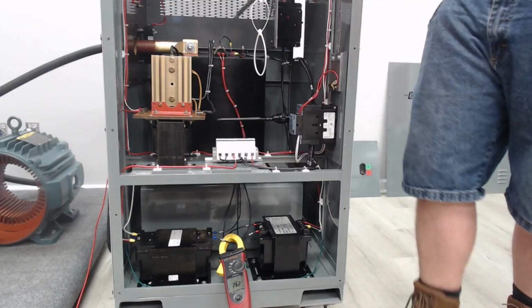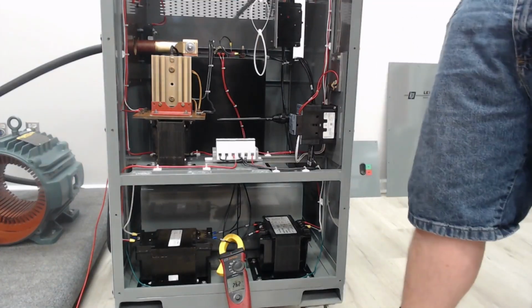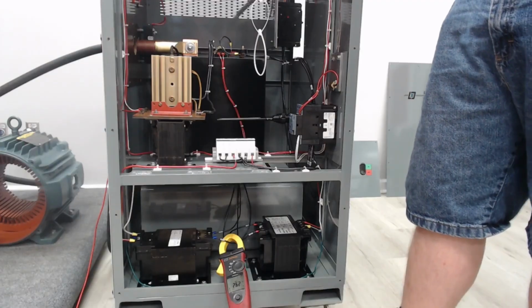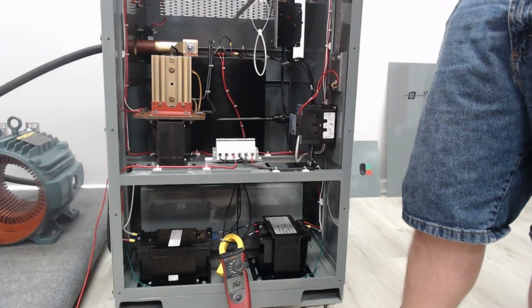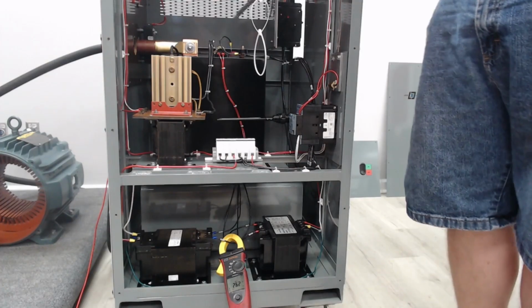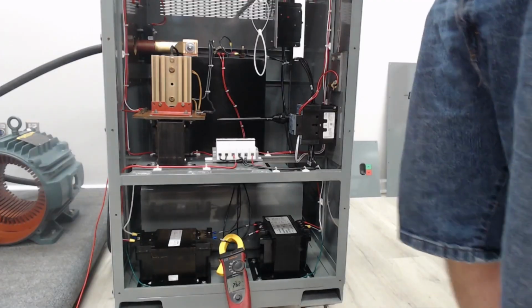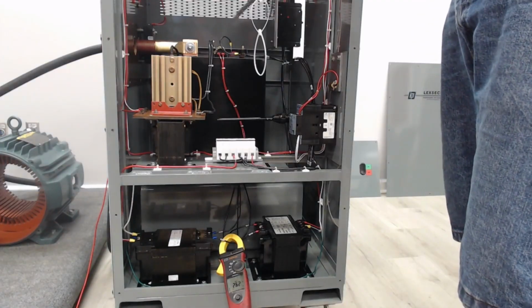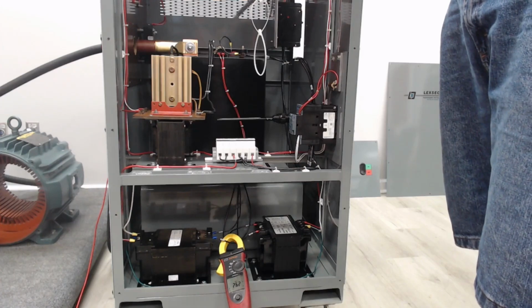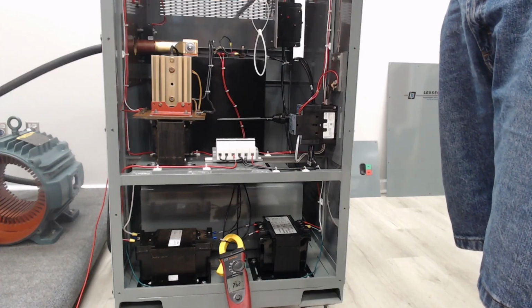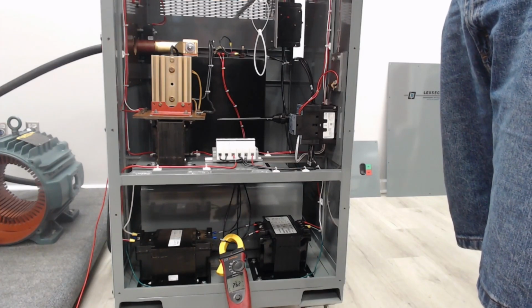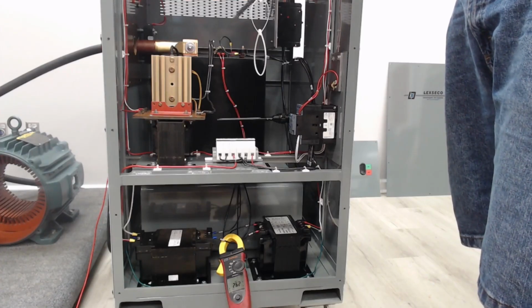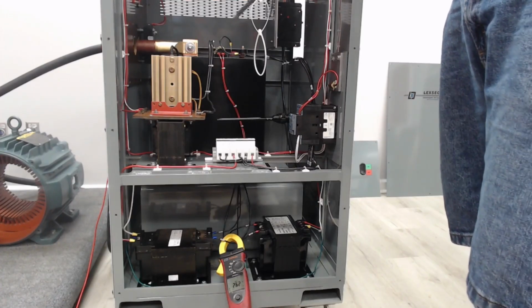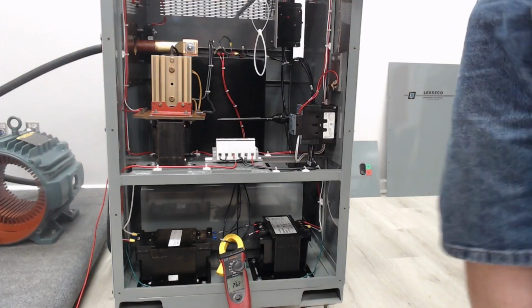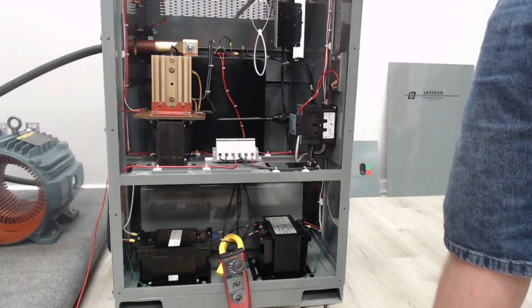The unit's designed to handle that, but if you're in a voltage drop, with insufficient power draw at your facility, then obviously it's going to blow that fuse. If you've got an old unit, where the transformer is 10 years old, it's just not as efficient. So getting a new transformer can help. You'll get a little bit less of a loss there, and it'll lower that amp rating, so that can help, but that's going to be on an old unit. New units shouldn't be dealing with that problem.